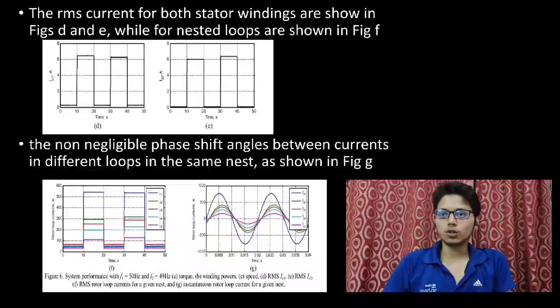The RMS currents for both stator windings are shown in this figure, while those for the nested loops are shown in this figure. It is evident that the outer loops of the nest carry much higher current than the inner loops, which can cause an unequal current distribution. This unequal current distribution between different rotor bars yields unequal rotor heat distribution. It can be tackled by using rotor bars with different cross-sectional areas: larger for the outer loops and smaller for the inner loops.